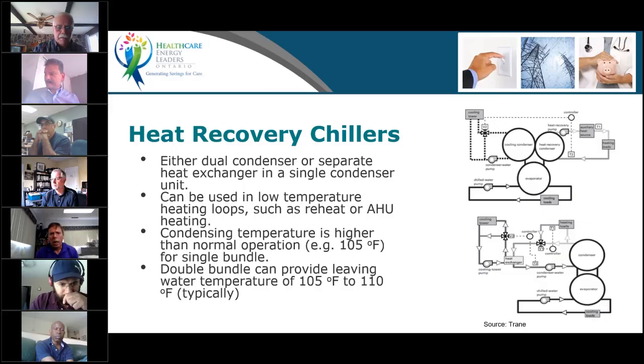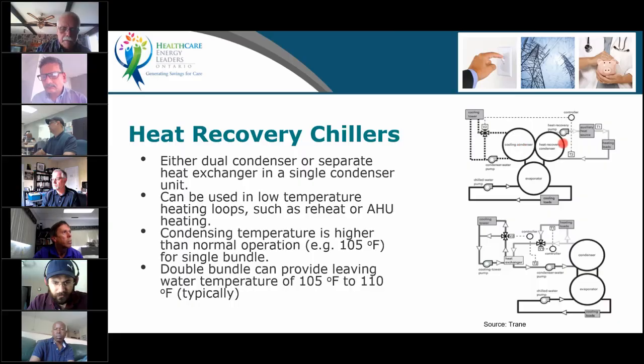We talked very slightly about heat recovery chillers. You have two types of configuration. I'm making it simple here. You've got what we call the double bundle chiller, the one at the top here. The reason it's called double bundle is because it has two condenser bundles, one for regular operation and one used for heat recovery operation. Not all manufacturers now make double bundle chillers. So what you can do is have a regular chiller, but an external heat exchanger that will provide you with your heat recovery.